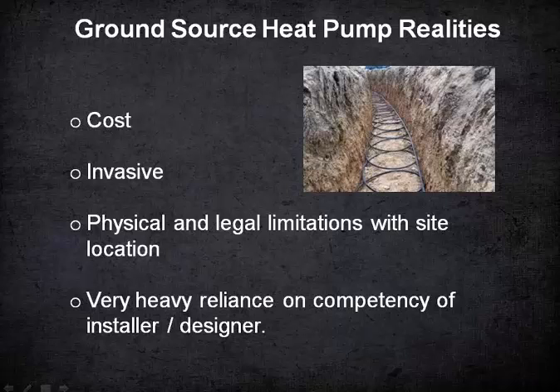And same note, depending on soil conditions and where you're at, I also strongly would recommend the trimming pipe as a soaker unit. Used to put them in, did more verticals than I did horizontals, but since being at Energy Dynamics, had the opportunity to go out on a problem system a few years ago. The system was 16 years old and never running hot temperatures in the summertime. They happened to have put in a trimming pipe. We put 30,000 gallons of water in the ground. System started working like a champ. I'll bet. It's amazing what a little bit of moisture does to conductivity. Yeah, it is. So back to you, James.